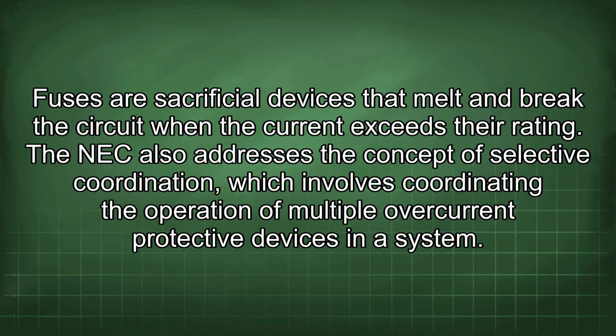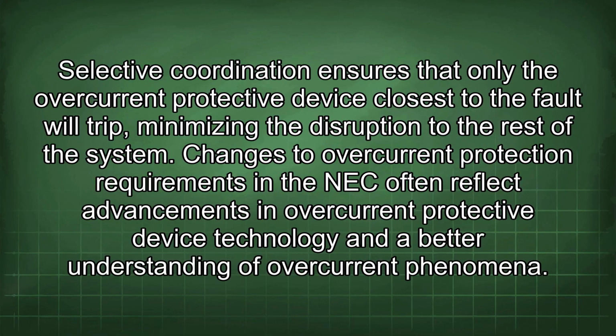The NEC also addresses the concept of selective coordination, which involves coordinating the operation of multiple overcurrent protective devices in a system. Selective coordination ensures that only the overcurrent protective device closest to the fault will trip, minimizing the disruption to the rest of the system.